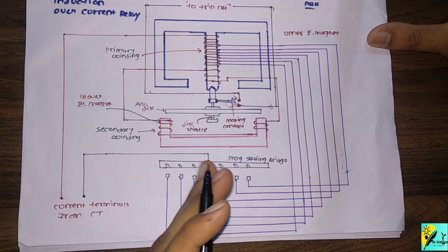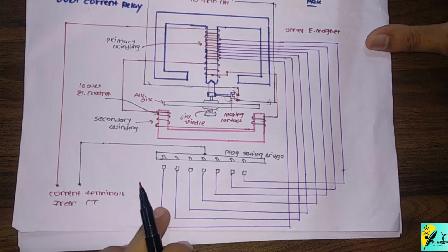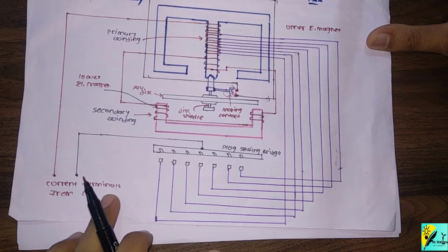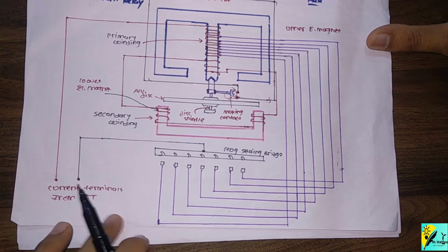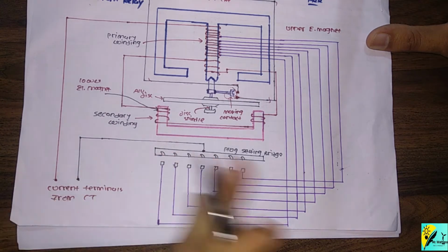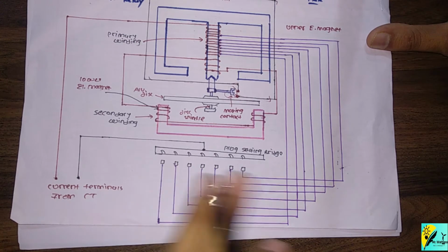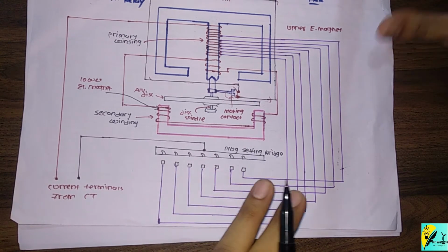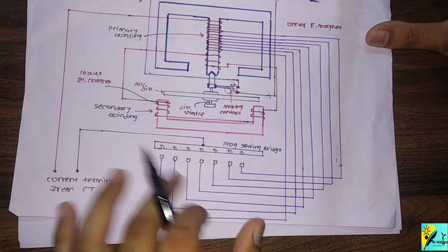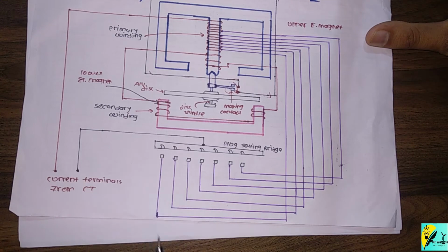The rating may be 10 ampere, so it can be connected to a CT with a secondary current rating of 10 ampere, but with a 50% setting the relay will start operating at 5 ampere. Adjustment of the current setting is made by inserting a pin between the spring loaded jaws of the bridge socket, at the proper tap value required.